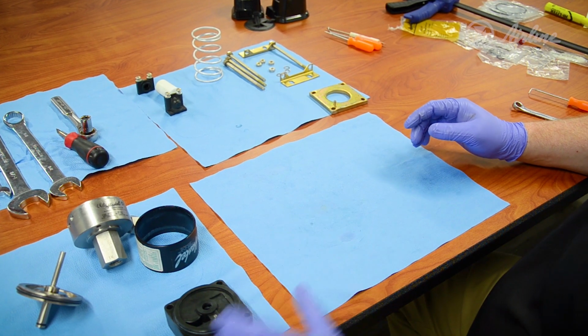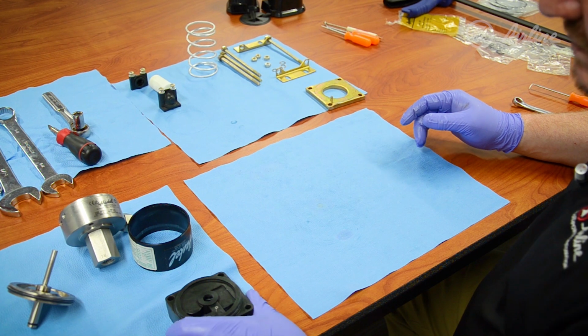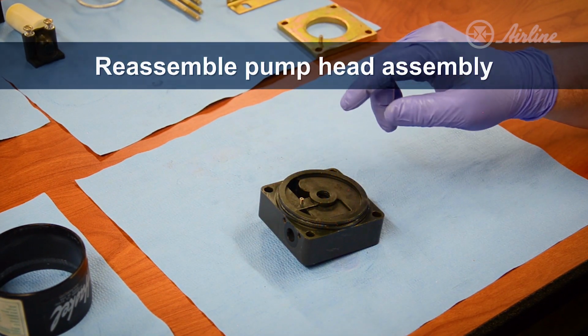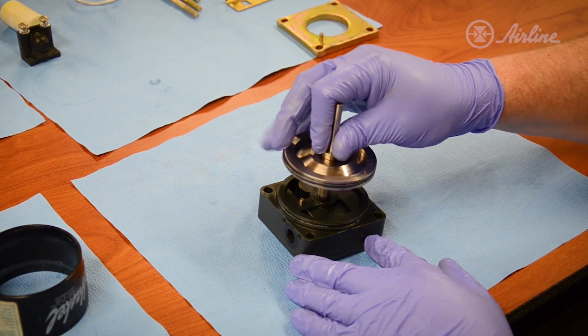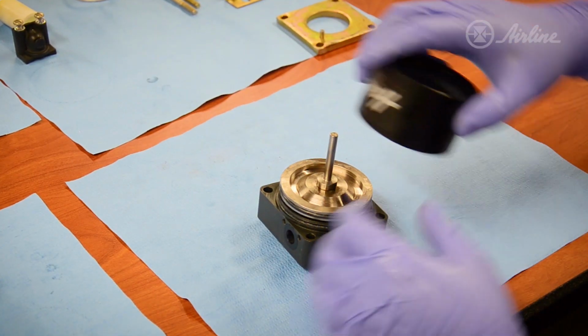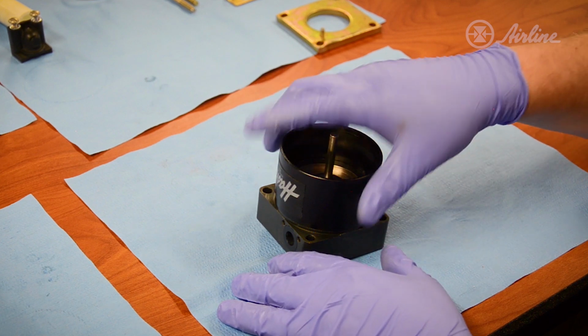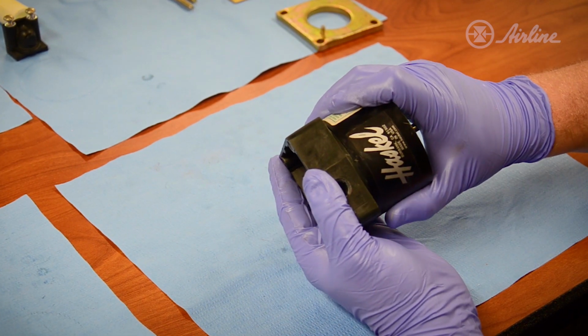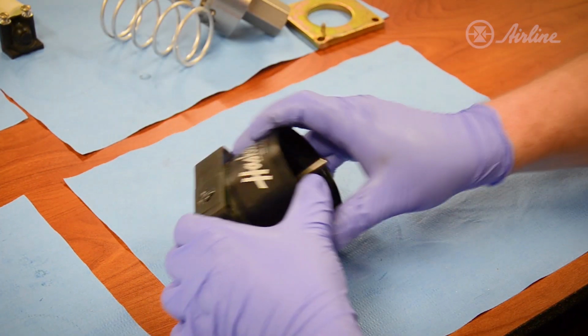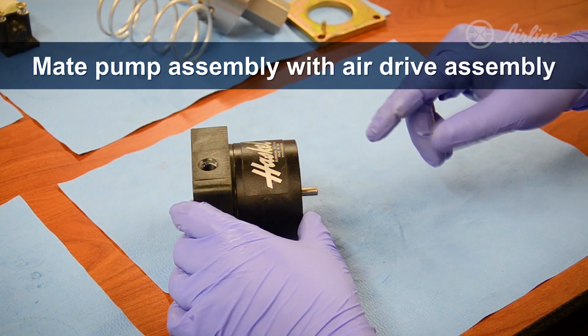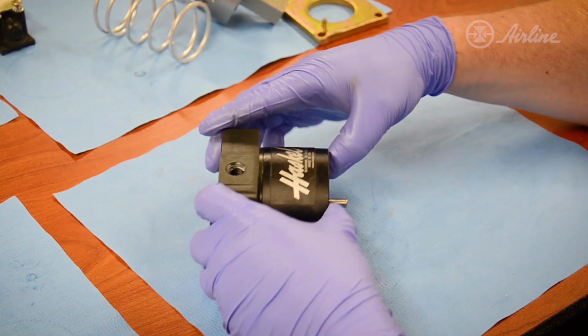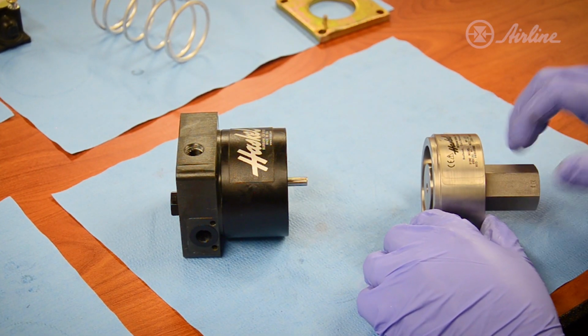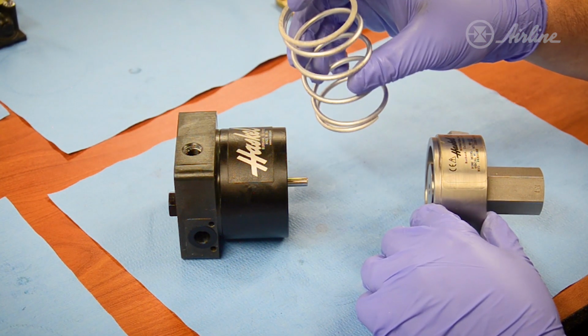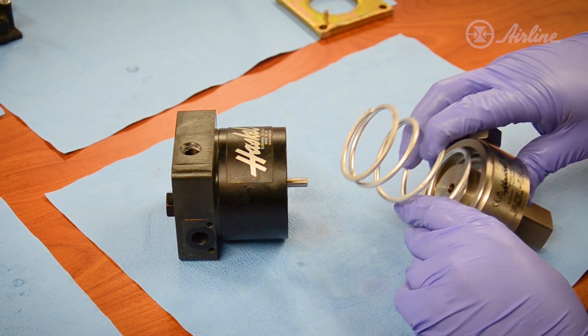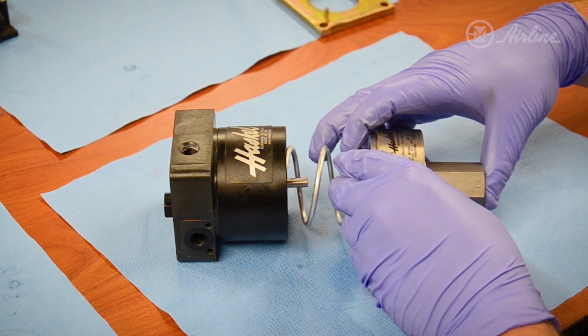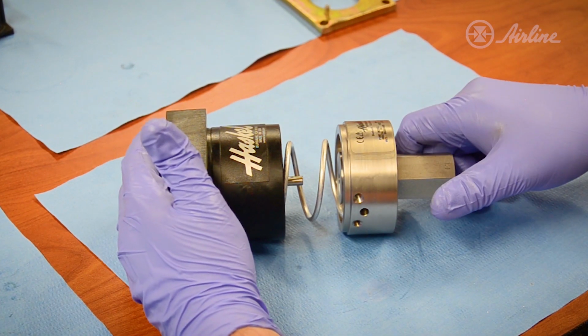Now we're ready to start reassembling all of the major pump components back into a completed pump assembly. Here we'll start with the pump head assembly. We'll add our plunger assembly, and over top of those we will carefully install the air drive barrel. Once we have that installed, we'll realign our alignment marks on that assembly. Now we're ready to get the pump assembly ready to mate back to the air drive assembly. We'll place the air drive with our match mark facing up and the pump assembly with its match mark facing up here. Now we'll take the return spring, put it in the return spring seat in the pump head, and mate that up with the return spring seat in the plunger assembly.